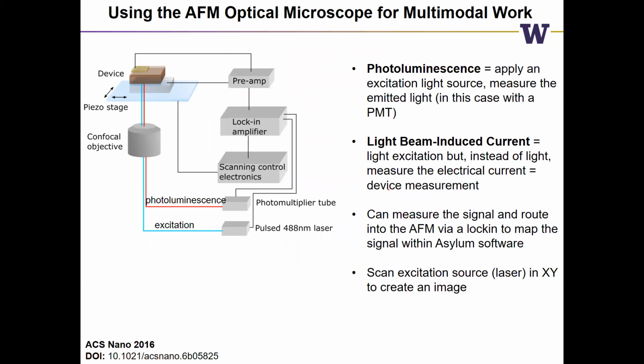I should note that the reason we have this PL setup, and this is an image from Giles and David's paper a long time ago, is so we could do PL in the AFM that we already talked about. You can also do light beam induced current. That's where you're shining a light confocally across a sample, but instead of just measuring an optical response, like the wavelengths being emitted or the sum of light being emitted, you measure the current. So it's a way to do device measurements point by point, and you can use the AFM scanner to do that pretty easily and efficiently. And you can do quite a wide range of other things.